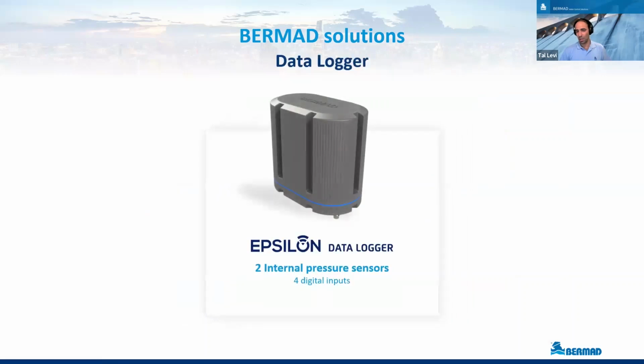It's much recommended to complement pressure management with a data logger at the critical point. We have a version of the epsilon that can be located at that point to measure pressure. Mostly, what's needed there is just measuring a single pressure point, but this epsilon version has two internal pressure sensors and four digital inputs, so if there is a water meter, it can be connected as well. That's the complementary product at the critical point.